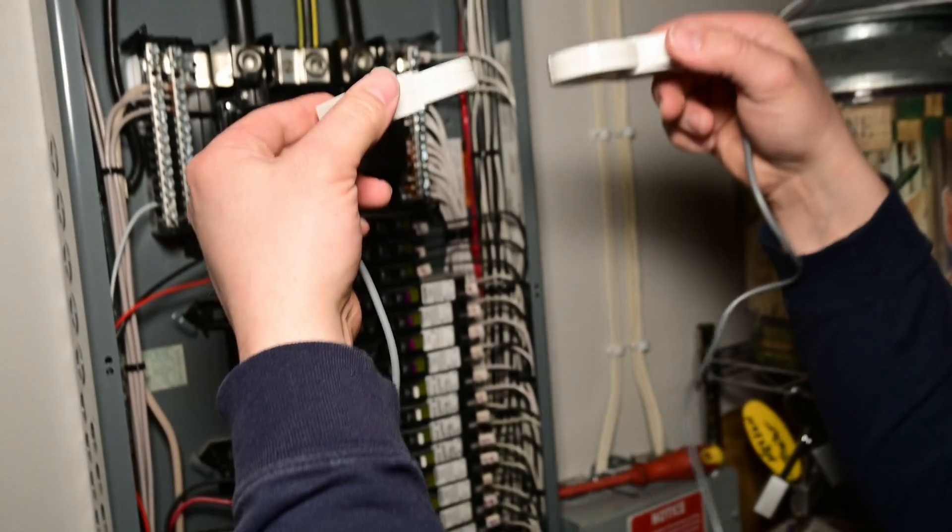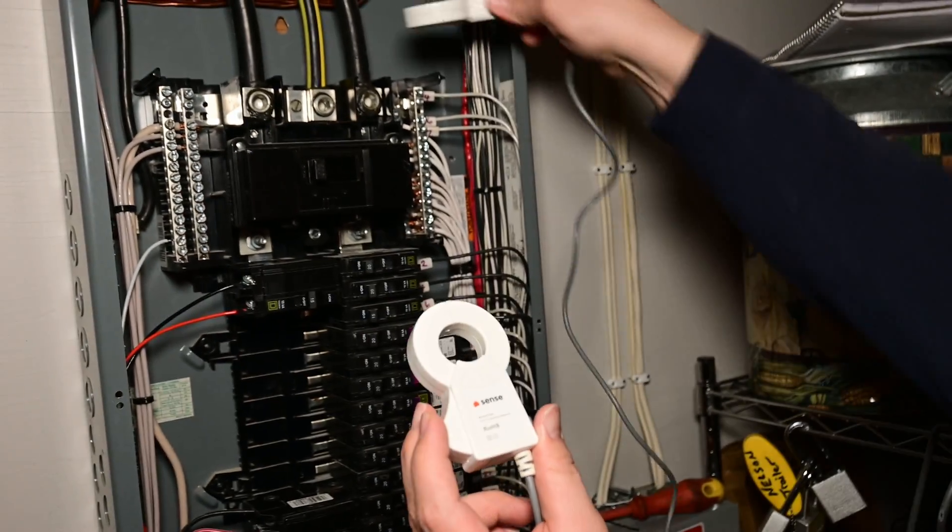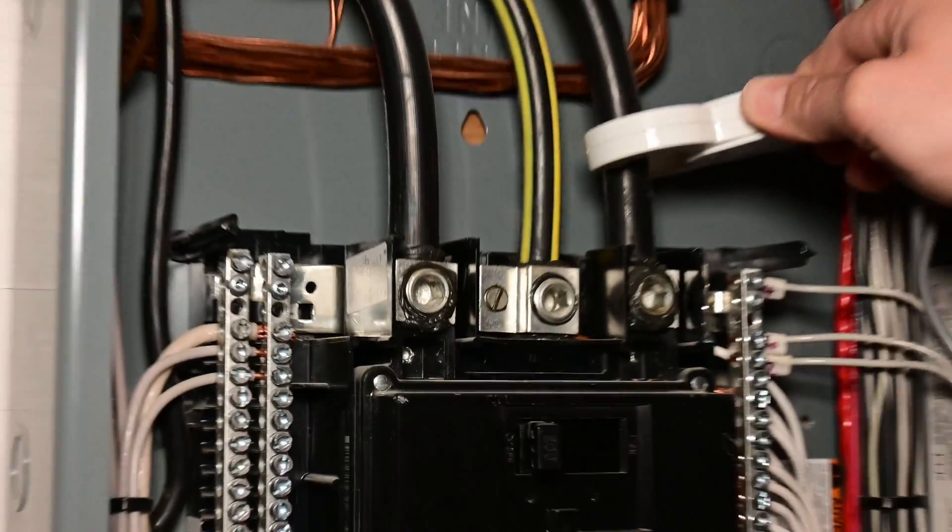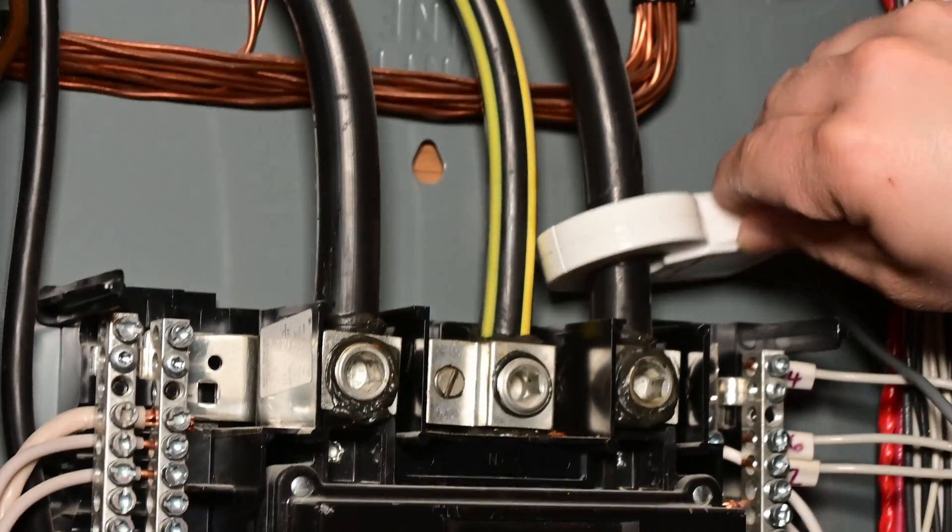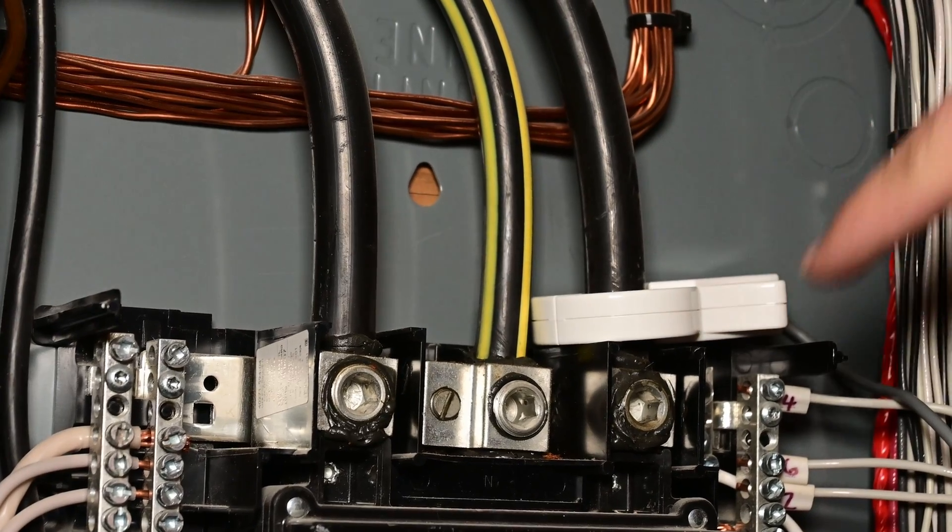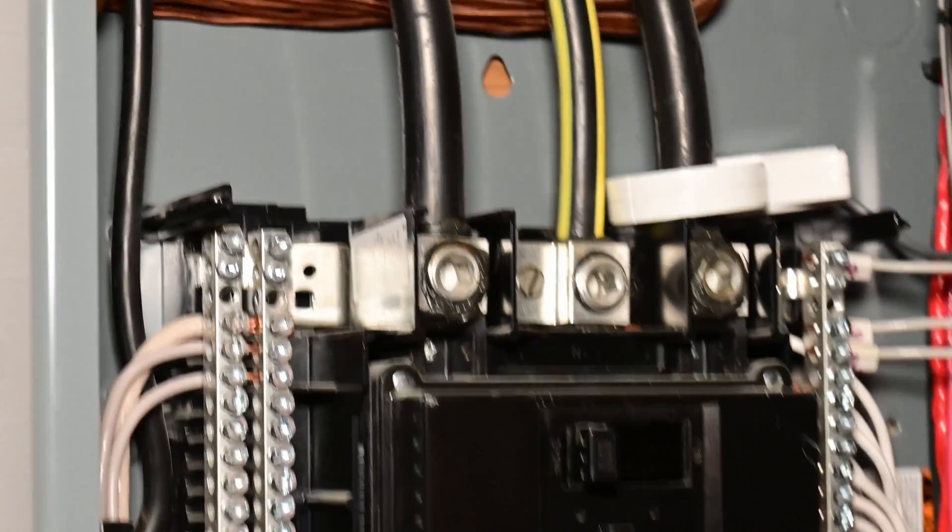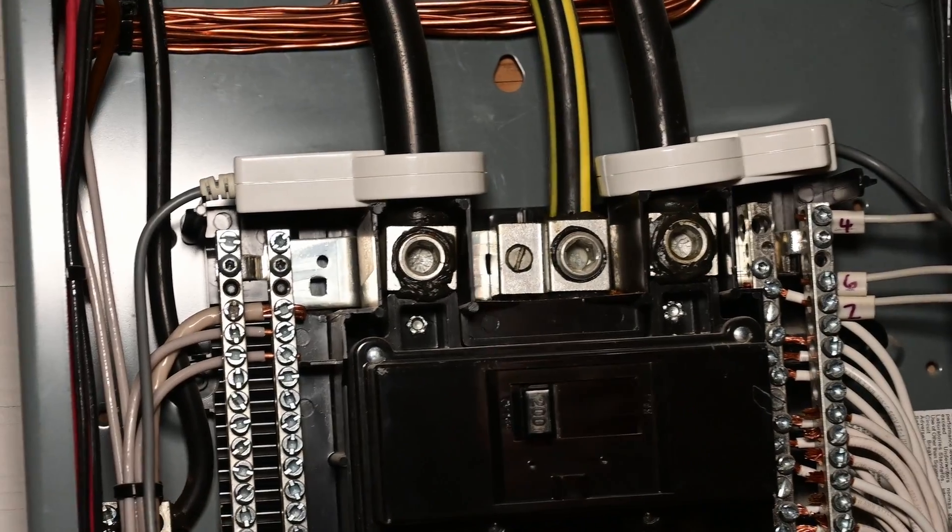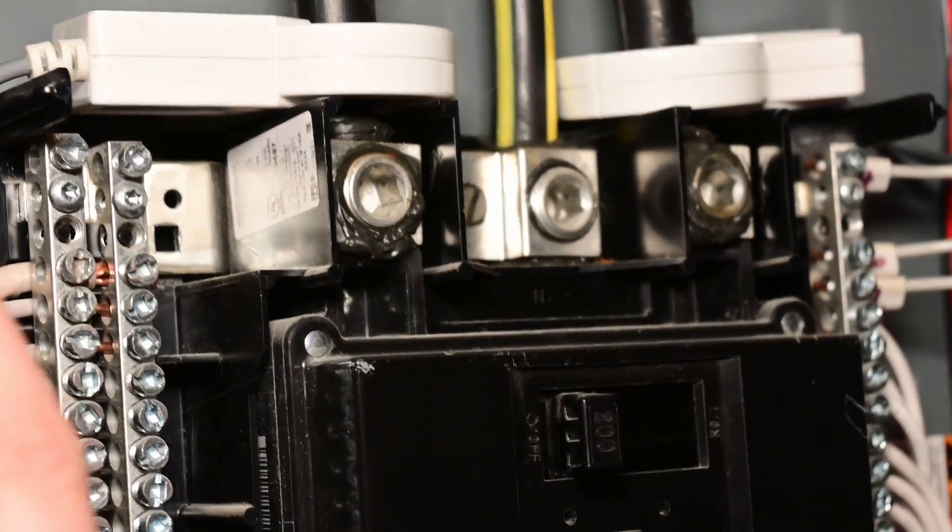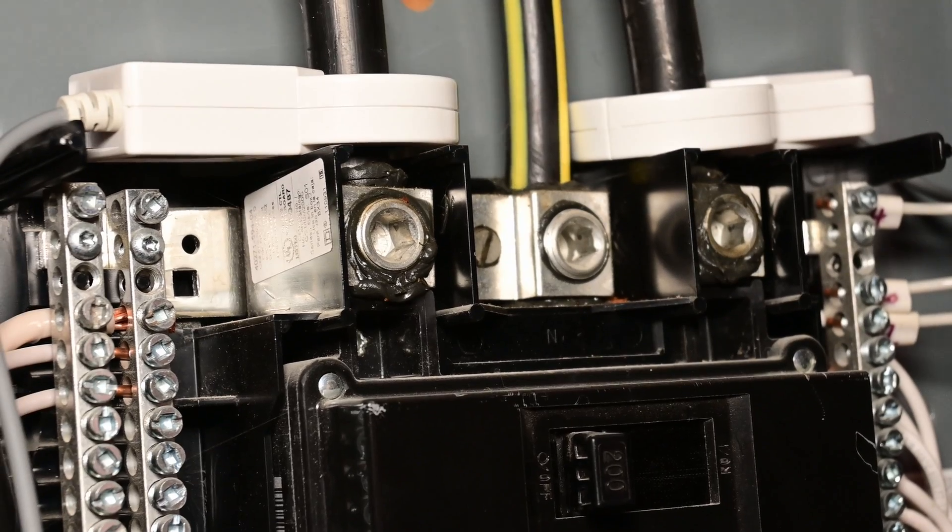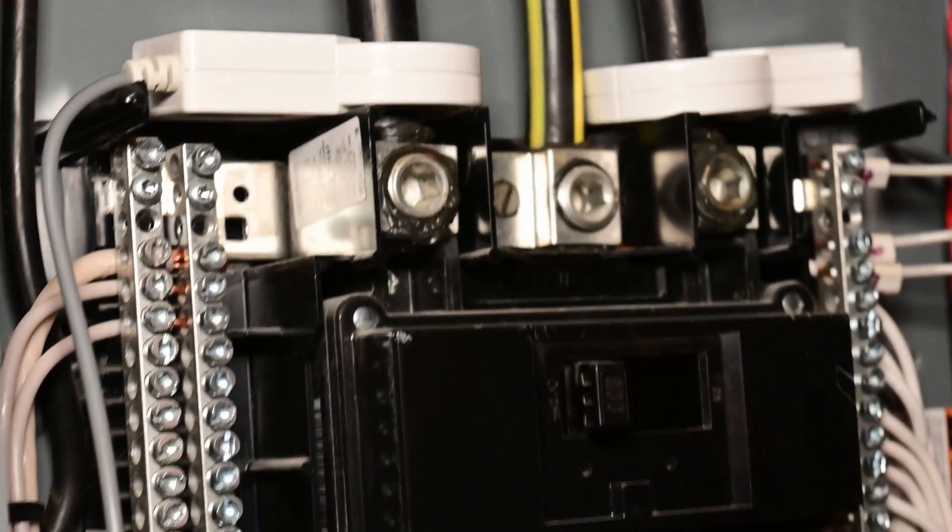We're going to clamp these around each one of these legs. I'm just going to use one hand because these are still live right here. That's still live power. If I were to touch that, it would be very unpleasant. I'll clamp my second one around the other side. You just want to make sure that there's enough room so that they can fully close, and then you can rotate them back so that they are out of the way and that the panel cover will still be able to be put in place.